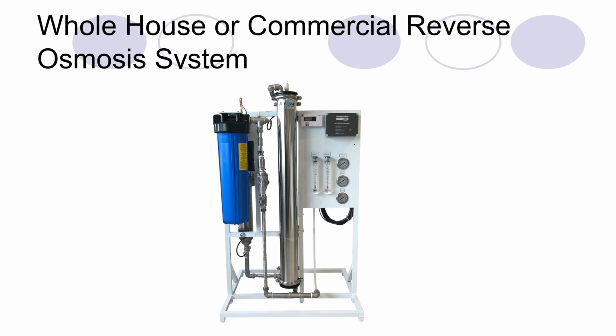If your question was, can you remove a 50 gallon per day membrane and substitute a 100 gallon per day membrane to get twice as much flow, the answer is no, because there's other things in the system, the flow restrictors and a few other things that would have to be compatible with that 100 gallon per day membrane as opposed to the 50 gallon per day membrane.